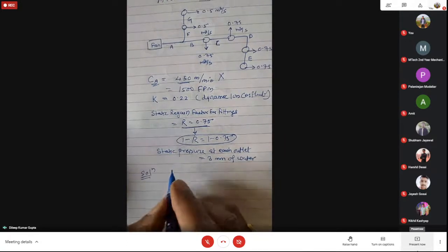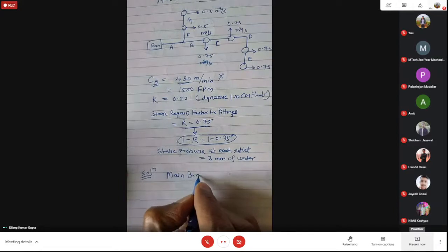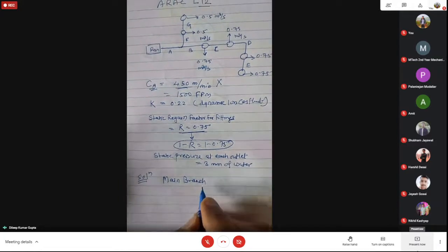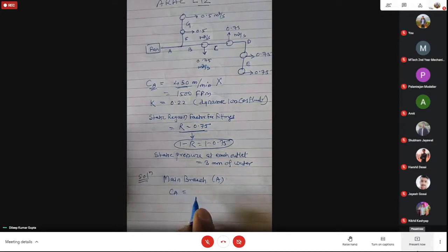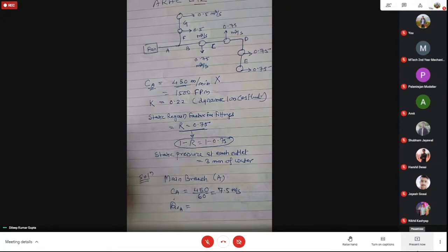Yes, sir. So we'll talk first about the main branch. We'll start with the main branch. Main branch will always be the first branch. So A. We have the value of CA here. CA is given as 450 meter per minute. So divide by 60, you will get it in meter per second, and that comes to 7.5 meter per second, the velocity in the main branch. What is the volume flow rate at point A?